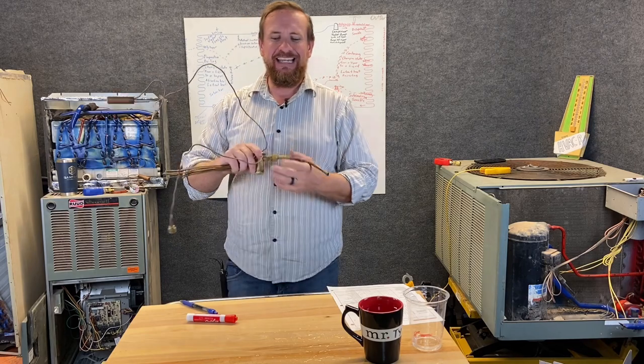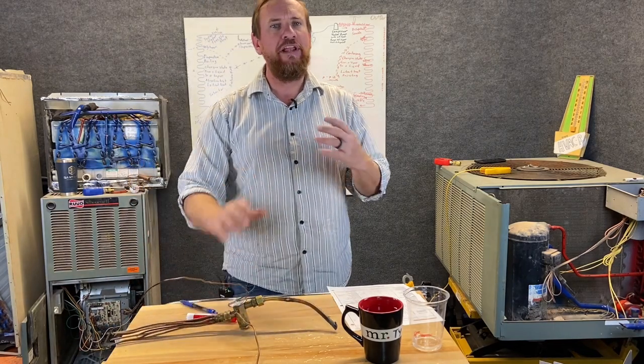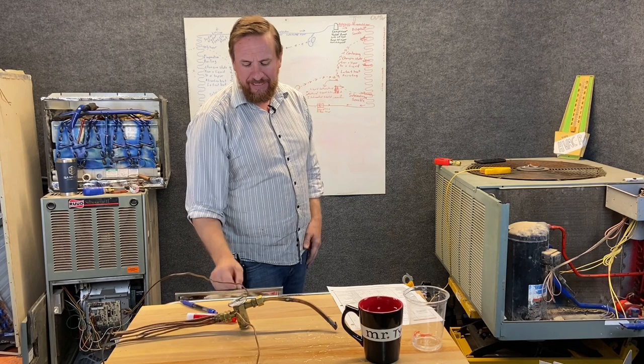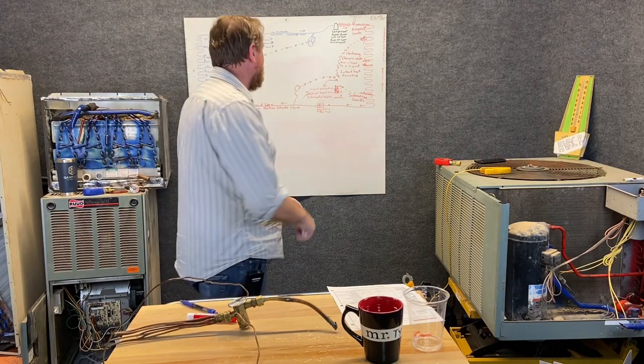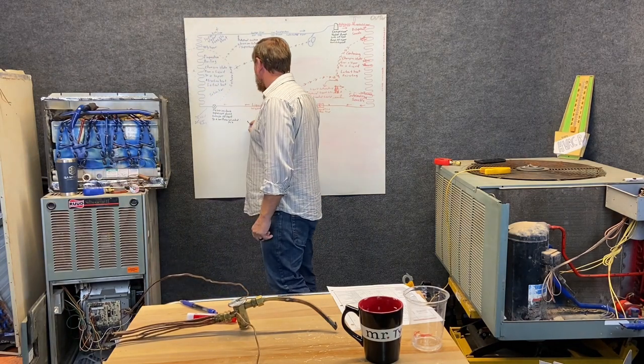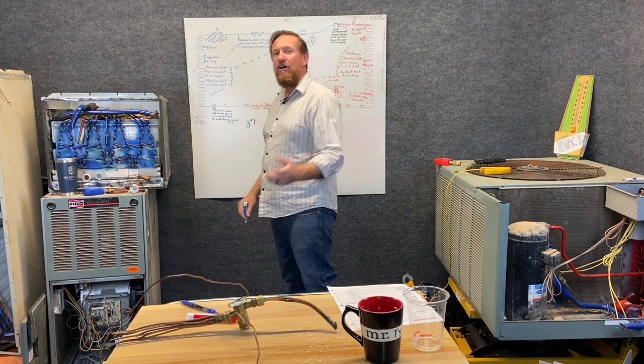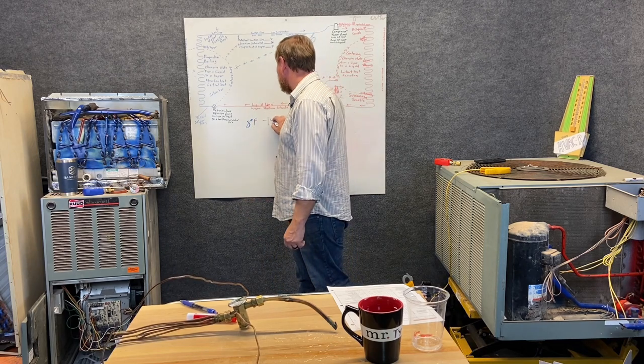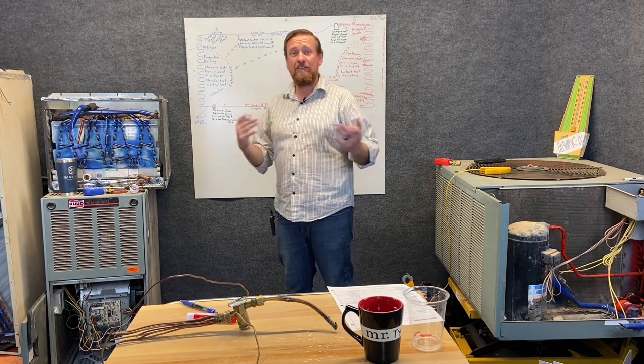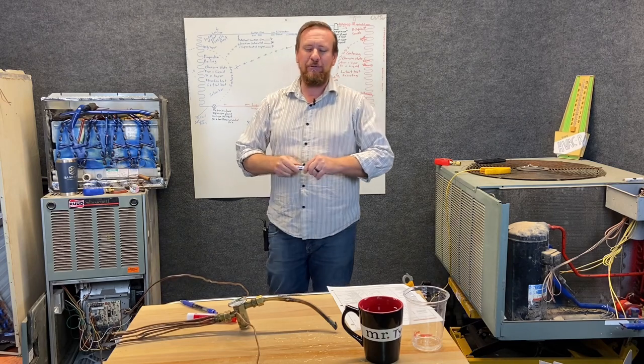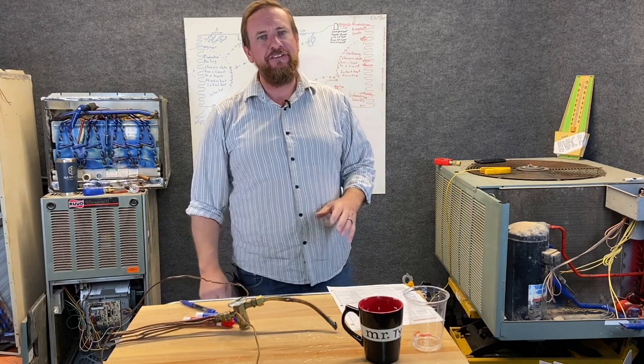So what we're going to need to know is a target superheat, what it's aiming for, what it wants it to be at. That varies greatly by different manufacturers. It can be as low as 8 degrees Fahrenheit or I've even seen them as high as 18 degrees Fahrenheit. That's quite a swing on superheat. So it depends on the manufacturer.